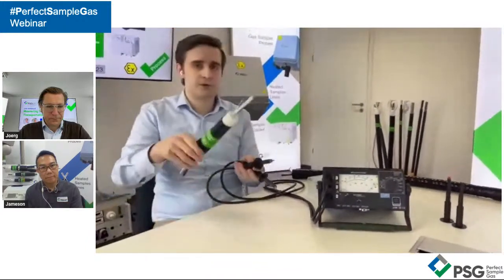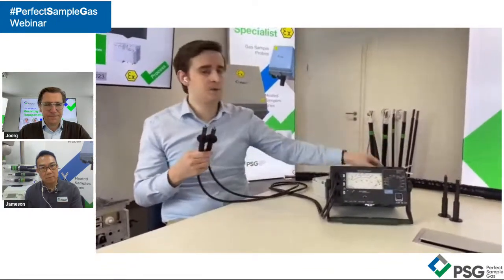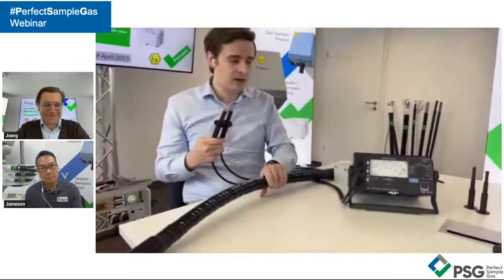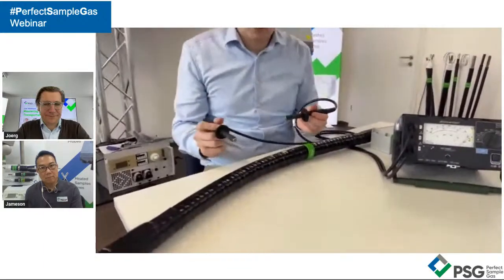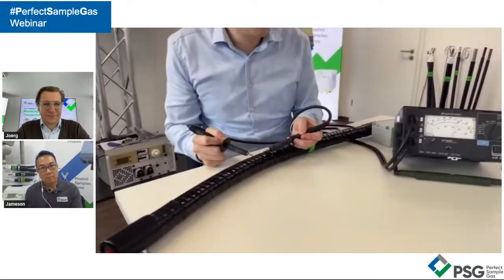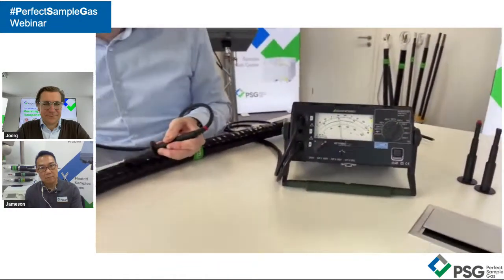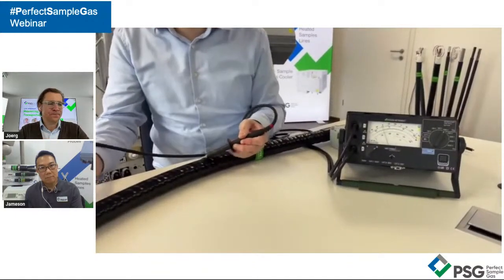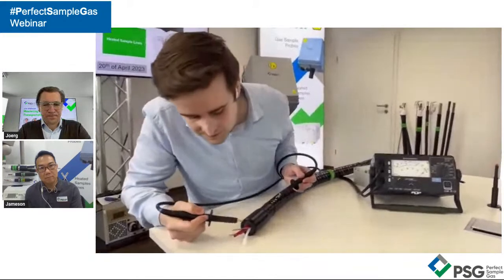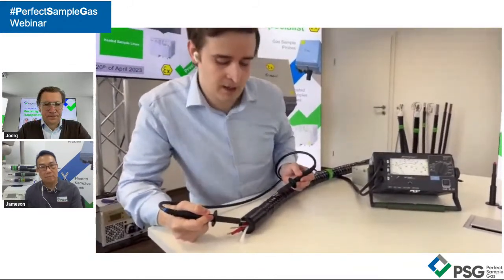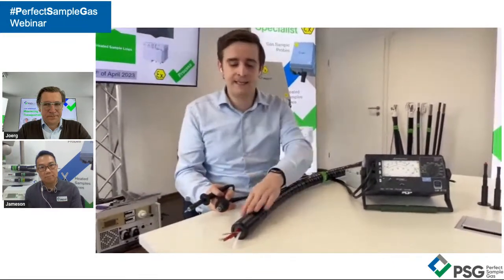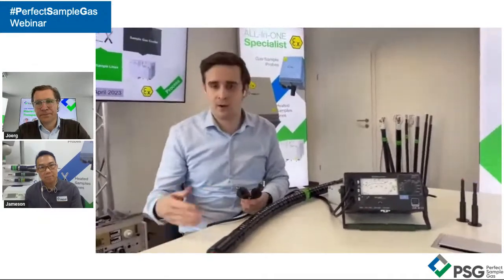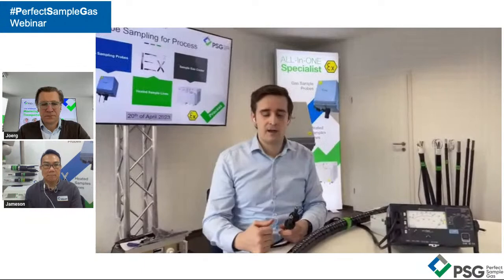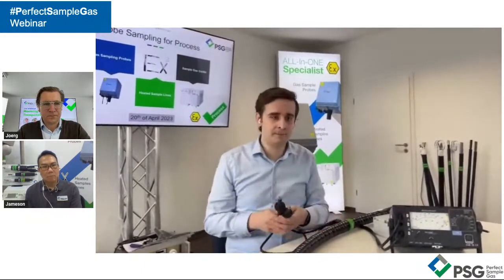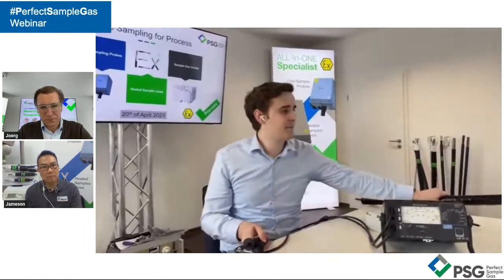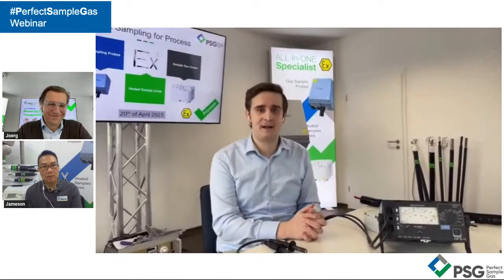So if you wouldn't use just a regular junction box in an ATEX area, why use a regular heated sample line for the ATEX area? Instead, we would recommend using our ATEX-3 heated sample line. When you go to the conductivity meter, there's a fully conductive jacket on the outer side, and the conductivity even goes up until the cap. So even the caps are conductive, and you can place these caps yourself. You can cut it to length, or we can also place the caps for you. And even when you cut it to length, you have the full ATEX certificate for the whole line. So this would be one of our heated sample line courses, a little excursus. Thank you very much for watching, guys, and have a good day.